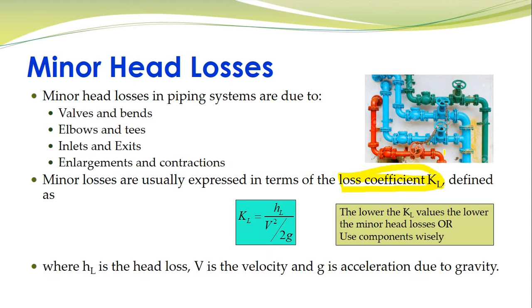So let's look at some examples of minor head losses. For instance, these are two elbows. Both of them will redirect the fluid at 90 degrees. In the first one we've got a sharp corner over here, so the KL value is 1.1. On the other hand we have an elbow which is rounded at the corners and it has a KL value of just 0.3. So just by making the corners smooth, rounded, we can significantly reduce the KL value. So I will use this elbow in the piping network when compared to this because it has a lower KL value.